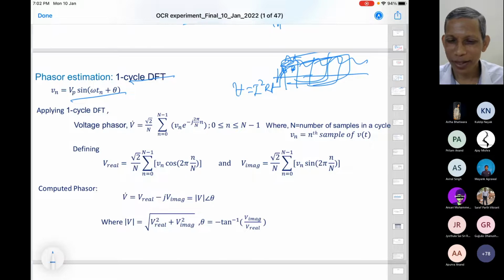So, unlike any mechanical system, you cannot wait for a long period and then make a judgment. To have fast or quick operation, this one cycle window, called the moving window, is shifted every time the relay acquires a fresh sample. Within that intersampling interval of delta t, the relay has to acquire the sample and also compute: is it a fault situation? That question it always asks. It means it has to rerun its main algorithm, always. That is the main difference in the case of a numerical relay.